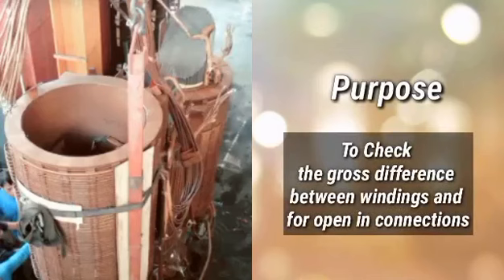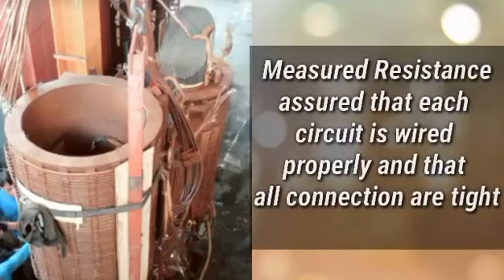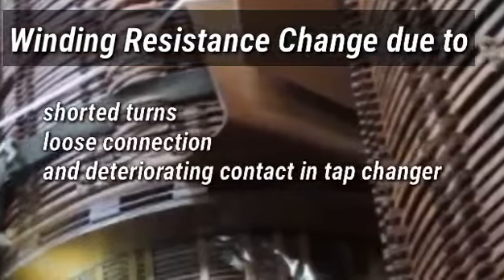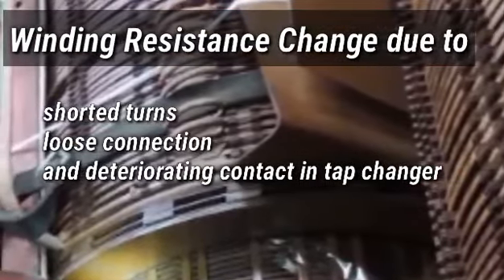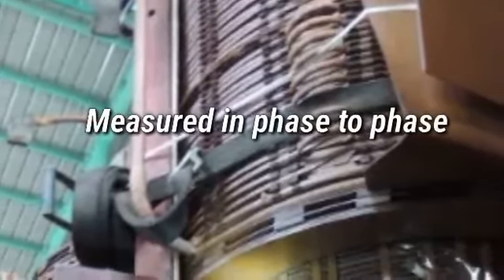The main purpose of this test is to check for gross differences between windings and for opens in the connections. Measuring the resistance of transformer windings assures that each circuit is wired properly and that all connections are tight. Winding resistance in transformers will change due to shorted turns, loose connections, or deteriorating contacts in tap changers. Regardless of the configuration, the resistance measurements are normally made phase to phase and the readings are compared with each other to determine if they are acceptable.